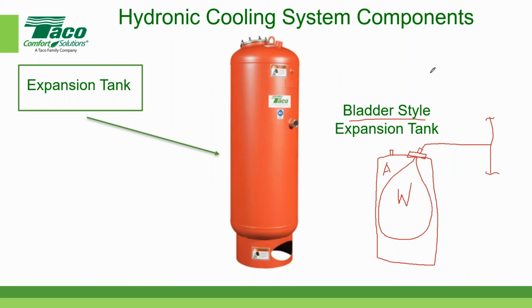And expansion tanks are responsible for a couple of different things. A lot of folks think they're just responsible to accept the expanding fluid as the fluid increases in temperature. But it's also responsible, in concert with the fill valve, to maintain the minimum pressure in the system. And properly sized, it's also designed to maintain the maximum pressure in the system. So the expansion tank does four functions. The fourth function is, if I look at a diagram, can I go back? Yeah, I can go back, right, Brett? Yep. Let me do that.